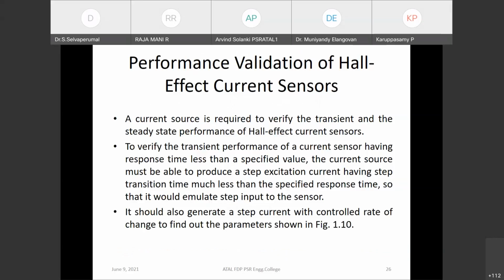Performance validation of Hall effect current sensors. A current source is required to verify the transient and the steady state performance of Hall effect current sensors. To verify the transient performance of a current sensor having response time less than a specified value, the current source must be able to produce a step excitation current having a step transition much less than the specified response time, so that it emulates a step input to the sensor. It should also generate a step current with controlled rate of change to find the parameters shown in the previous slide. The di by dt of the step current should be greater than the rated value to check the limitation in accurate di by dt.